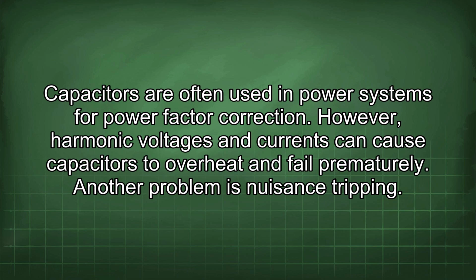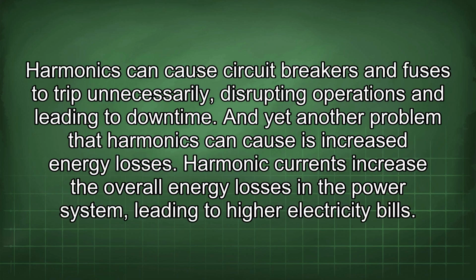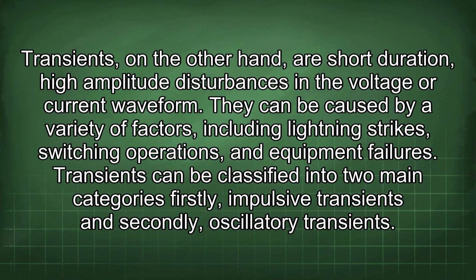Another problem is nuisance tripping. Harmonics can cause circuit breakers and fuses to trip unnecessarily, disrupting operations and leading to downtime. And yet another problem that harmonics can cause is increased energy losses. Harmonic currents increase the overall energy losses in the power system, leading to higher electricity bills. Transients, on the other hand, are short-duration, high-amplitude disturbances in the voltage or current waveform. They can be caused by a variety of factors, including lightning strikes, switching operations, and equipment failures. Transients can be classified into two main categories: firstly, impulsive transients, and secondly, oscillatory transients.